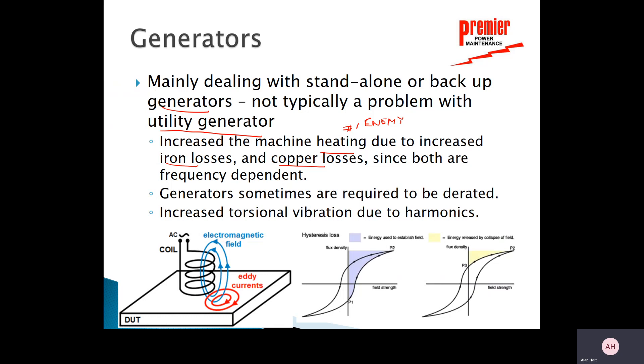Both iron losses and copper losses are frequency dependent. Sometimes equipment has to be derated — emergency backup generators or standalone generators may have to be derated. Transformers may also have to be derated to account for harmonics on the system. Because of harmonics, we'll see not only a heat problem but also vibration inside the unit, which is also problematic.